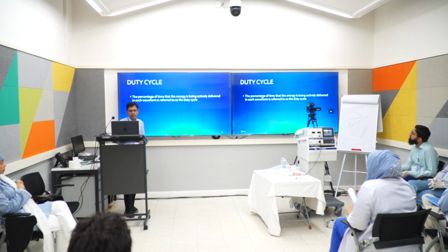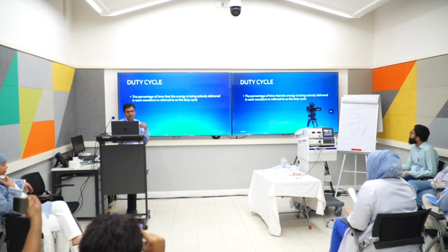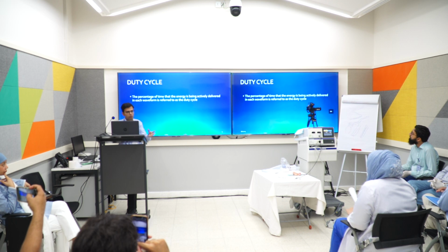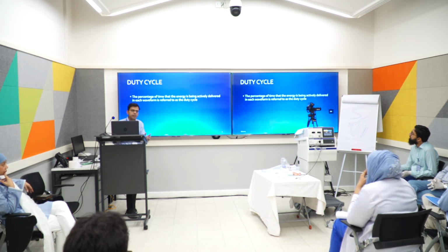What is duty cycle? Might sound a bit boring, but it's again very important, because this actually means the time the current flows uninterruptedly, right? If we define it, it's actually the percentage of time that the energy is being actively delivered in each waveform, be it cutting technique or coagulating technique. In simple terms, either the current is flowing uninterruptedly, or there are some interruptions in between. We will see how it defines the diathermy.